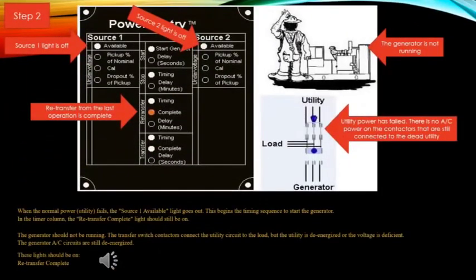In step two, the normal power has failed, and you'll see the source one available light is out. This begins the timing sequence to start the generator. In the timer column, the re-transfer complete light should still be on. There is no light that comes on to tell you it's timing for a start. The generator should not be running. The transfer switch contactors connect the utility circuit to the load, but the utility is de-energized or the voltage is deficient. The generator AC circuits are still de-energized.